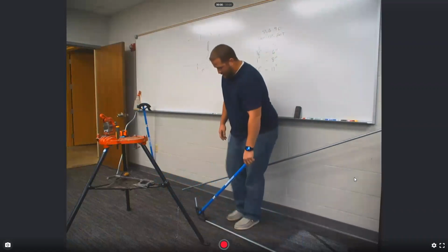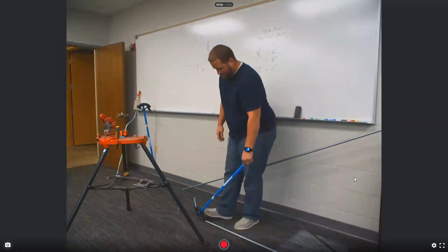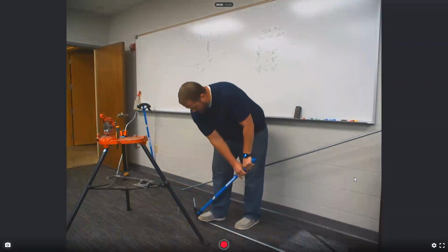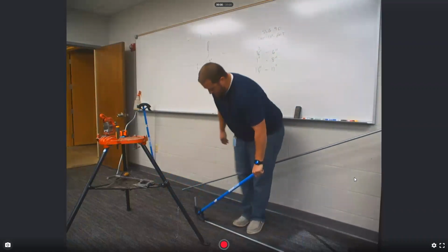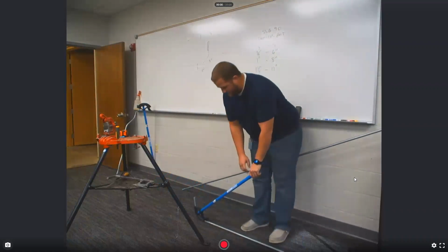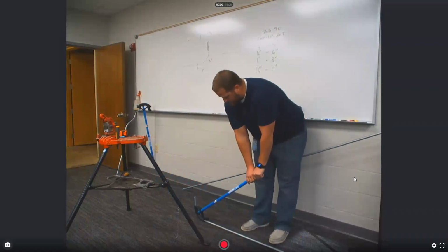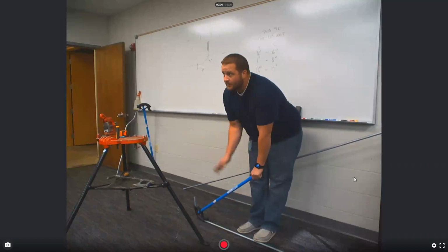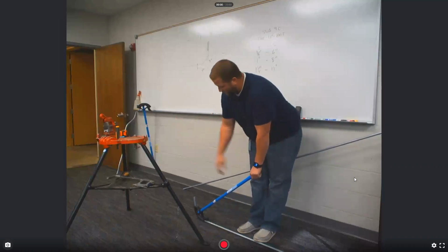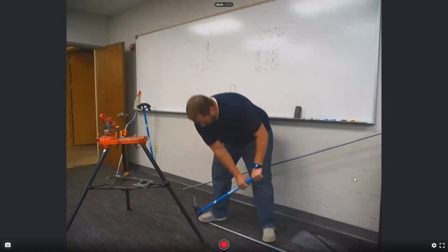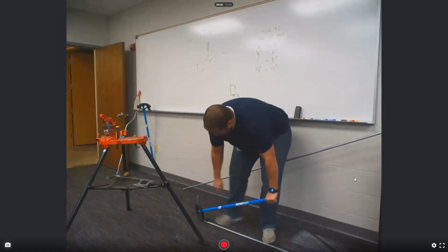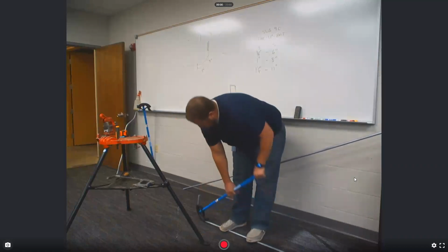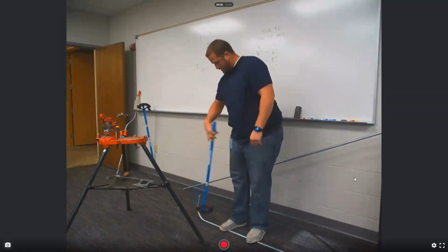All right, so then you want to put your foot on this little part of the bender and push down at the same time. The reason you do that is if I just push down on the end of the handle, do you see what starts to happen to the pipe down here? It starts to bend a little bit up and you'll get a little whoopty in your pipe. If you put pressure down and bend until you just barely feel the end of the shoe hit the pipe, you should be pretty close to 90 degrees.